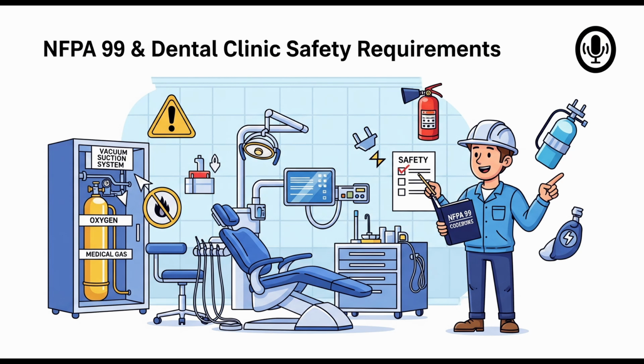Wow. Yes. And just as important, Section 15.4.2.4.9 explicitly forbids storing flammable materials, think flammable liquids like solvents, or cylinders of flammable gases like propane, in the same room or enclosure as your medical gas cylinders.